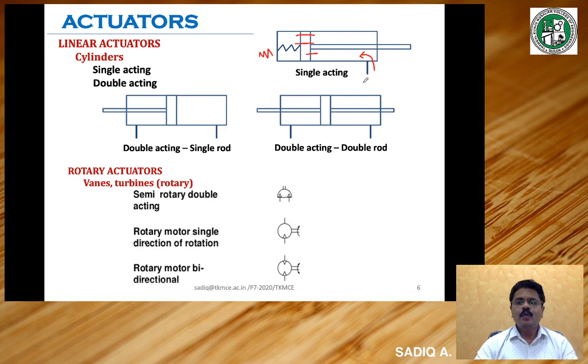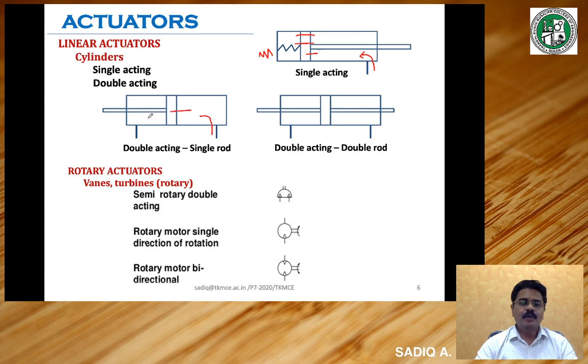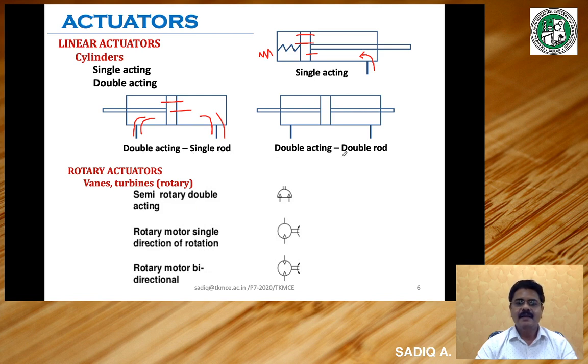In a double acting cylinder, there is power supply through both sides of the piston. The piston, piston rod, and two ports allow fluid to enter from either side. When fluid goes in from one direction, it pushes the piston that way, and the fluid on the other side drains back. The piston moves because of the pressure control between either side. There is also a sub-classification: a single rod double acting cylinder and a double rod double acting cylinder, where there are piston rods on both sides of the piston.